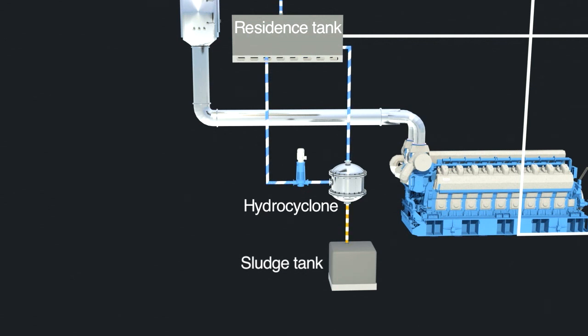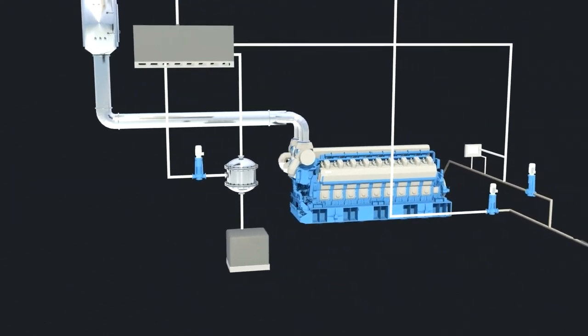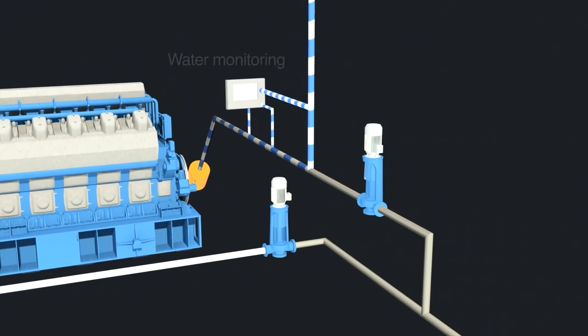The residue sludge from the hydrocyclones is led to a sludge tank. The non-hazardous sludge has to be disposed of at port and cannot be incinerated. The seawater is monitored for pH, temperature, and turbidity both at inlet and outlet.